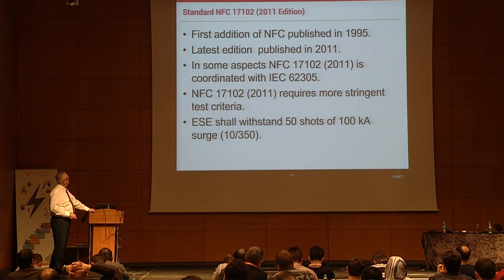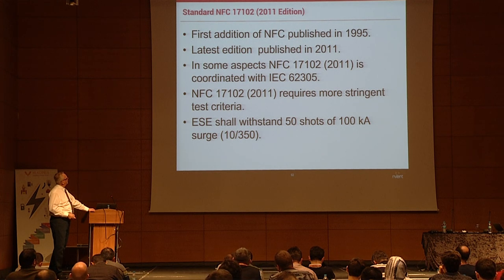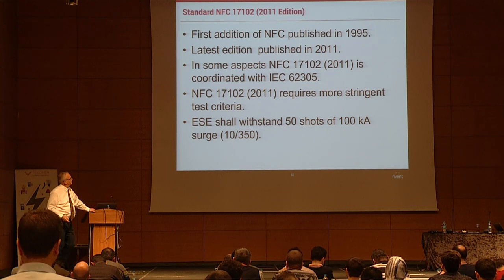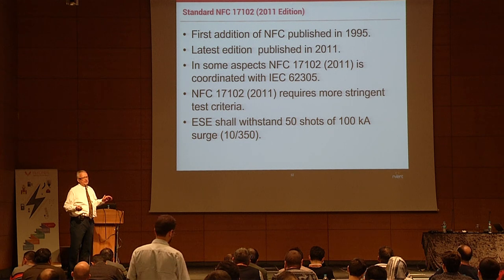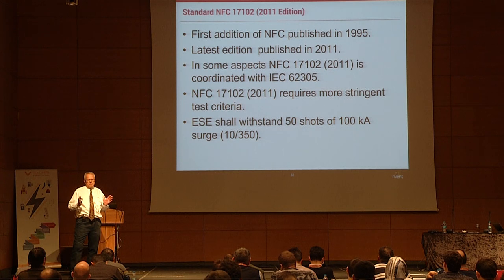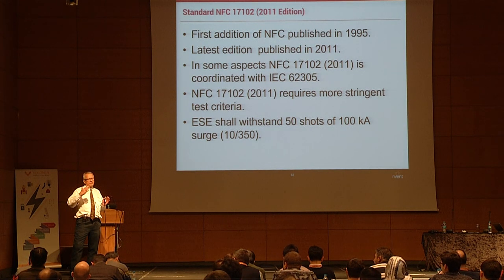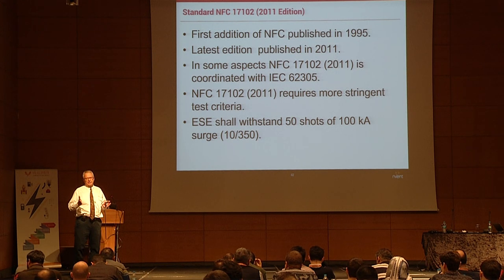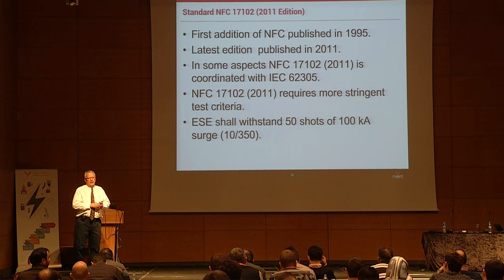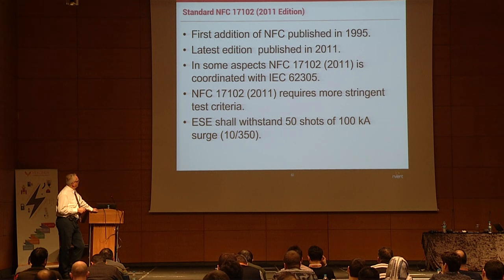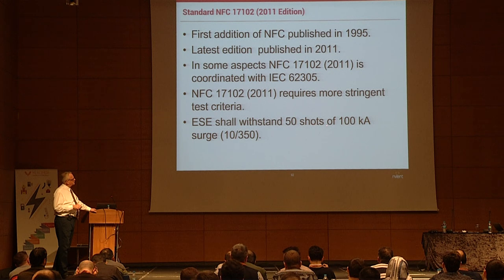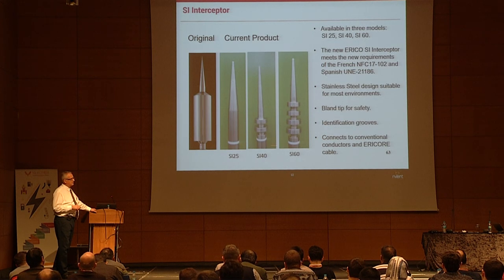The cable is well-suited for various applications. Now we'll talk about the French standard NFC 17102. The main change in the new version is that it references IEC standards for components — all components must be IEC-compliant. They also increased the test current; the system must withstand 50 shots of 100 kA of surge 10/350 waveform.